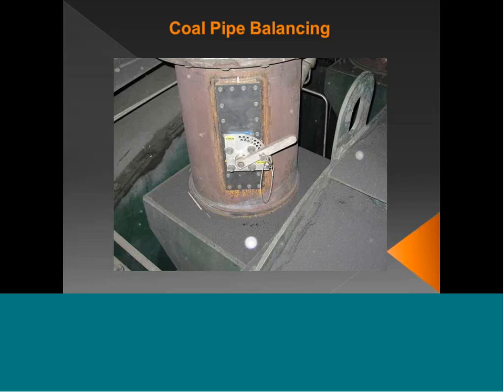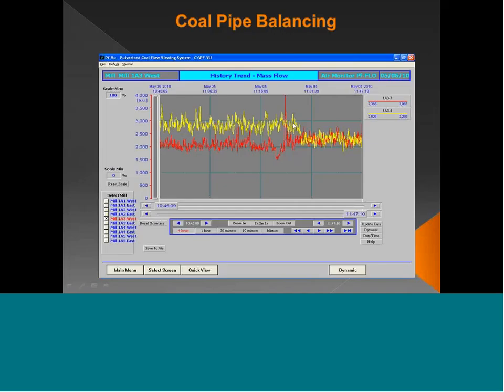This is a coal valve on the simplest system, a two-pipe system. This is one end of a double-ended ball mill, and so we have two pipes. We have the pipe in the near ground here and the pipe in the far ground here. This was a heavily loaded pipe, so the valve is closed. Here's the data from that move. This is a mass flow screen. We close down on the yellow pipe, and the coal goes to the red pipe.